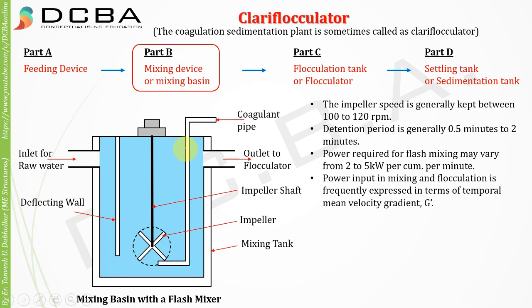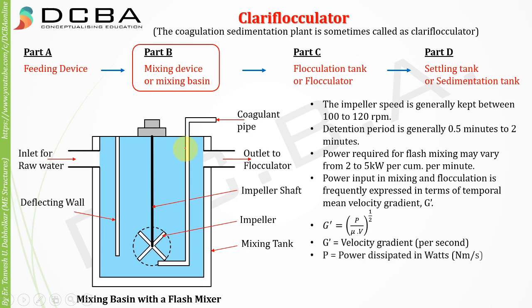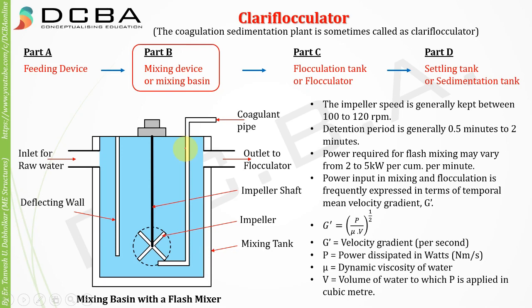Power input in mixing and flocculation is frequently expressed in terms of temporal mean velocity gradient G'. The formula is G' = √(P / μV), where P is power dissipated in watts (Newton-meters per second), μ is the dynamic viscosity of water, and V (capital V) is the volume of water — not velocity. G' is the velocity gradient, representing the slope of velocity between any two points, with units of per second (s⁻¹).